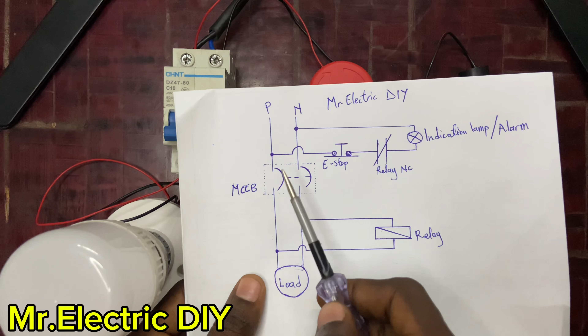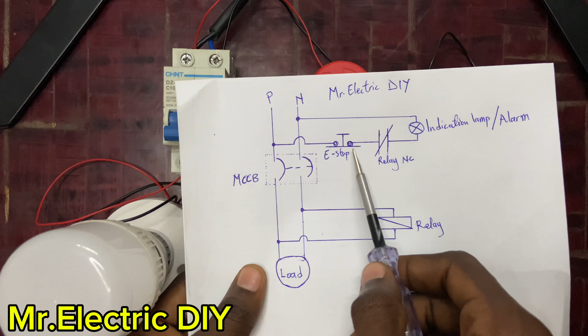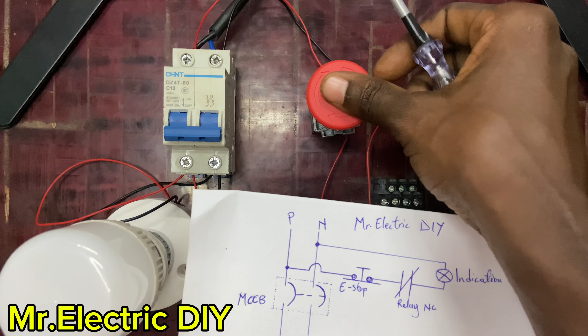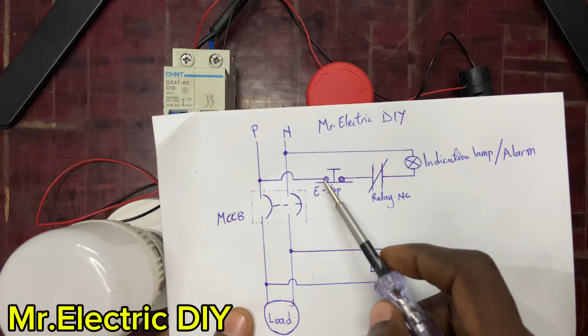Now what I have to do is to insert the coil. What you have to take note is that when you are connecting from this section, that's the phase, to the emergency push button, I have to make sure that this is normally closed. I have to make sure that when I push the push button, just now it is normally open. So if there is power here, the phase, then it is going to be trapped at this section. If you don't do it that way, the moment you connect from here to this side, because it's normally closed contact, the power will just flow from here.